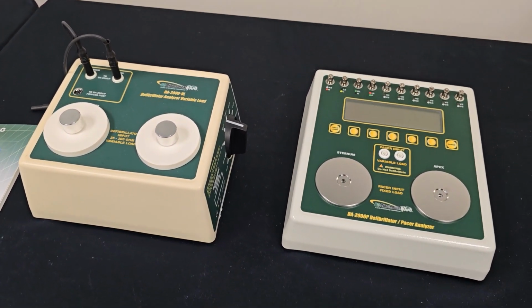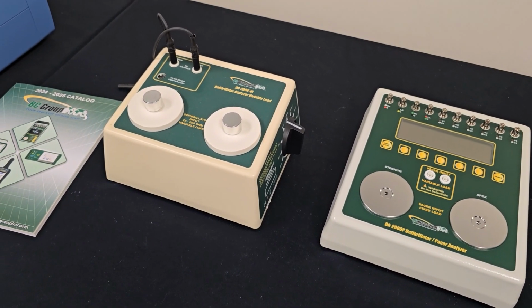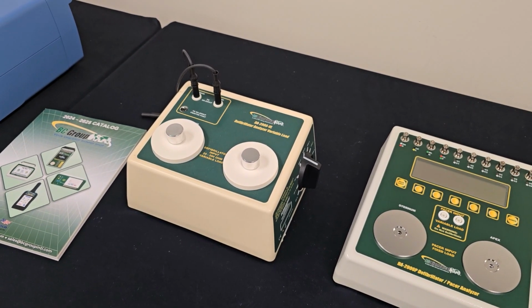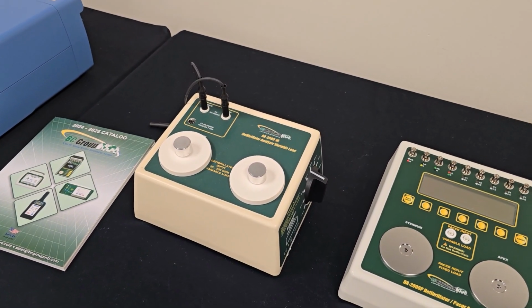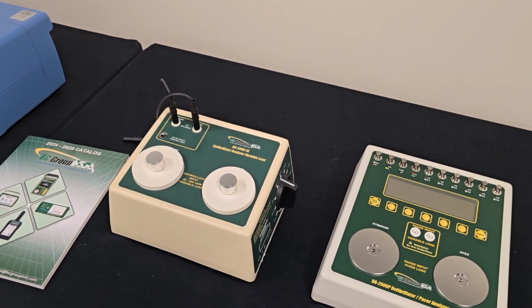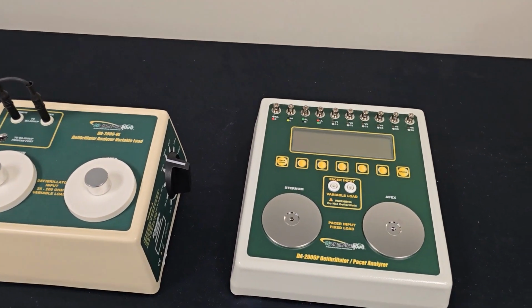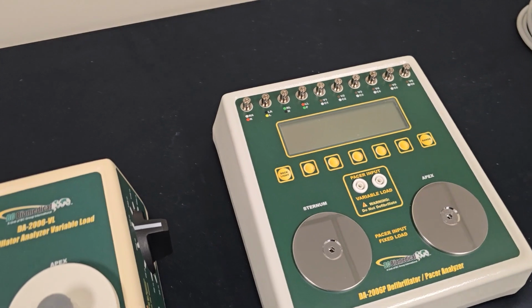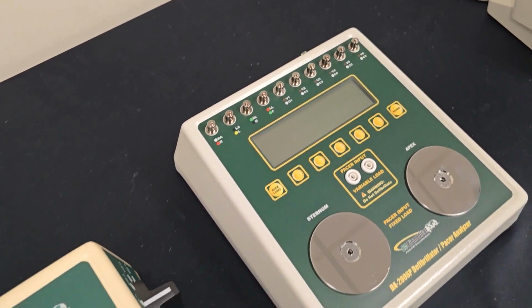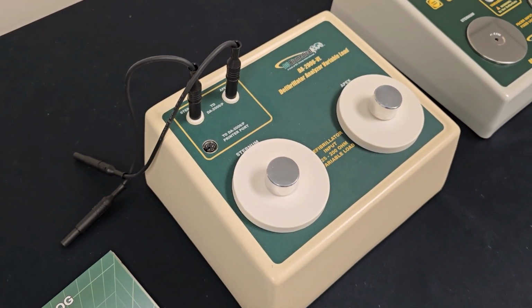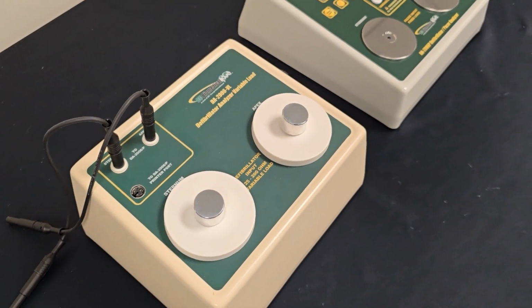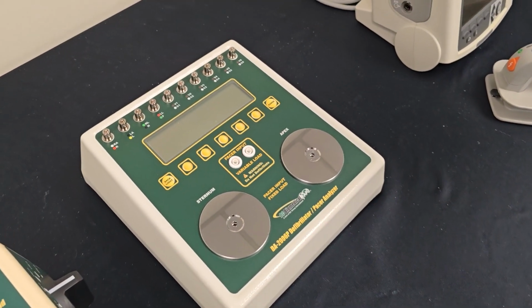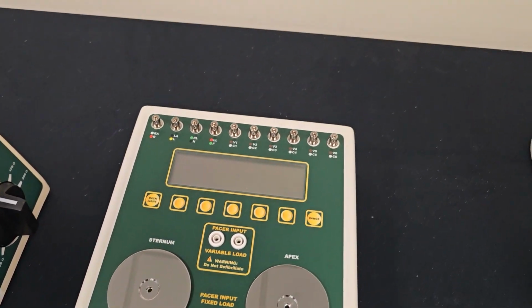Nice. And the advantage that we have over the competitor's product is that when you plug that into the defib analyzer, we can measure that load. And when you're running your test, you don't have to worry about, do I have my load configured correctly? Because it reads the load and it automatically compensates the measurement based on the selected load. Okay. DA-2000P analyzer.